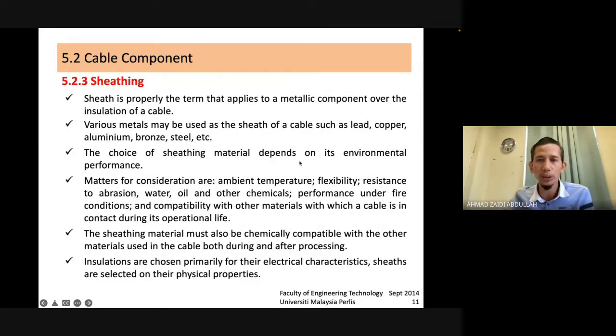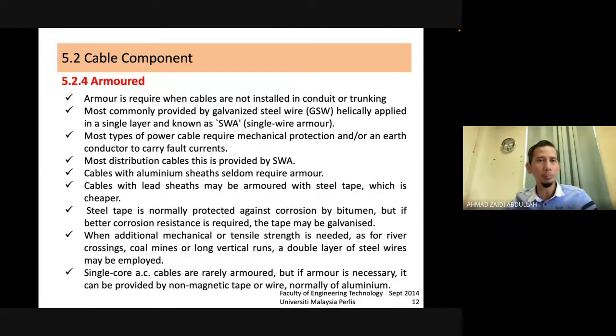So the choice of sheathing material depends on environment performance. And then the factors for consideration are ambient, flexibility, resistance to water, oil, and other chemicals. And then the sheathing material must also be chemically compatible. And the insulations are chosen primarily for their electrical characteristics, sheaths are selected on physical properties. Okay, armour, the second part. Armour ni armour perisai. So this one only have for underground cable. So armour is required when cable are not installed in conduit or trunking.